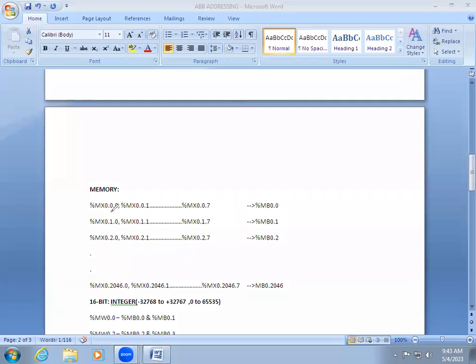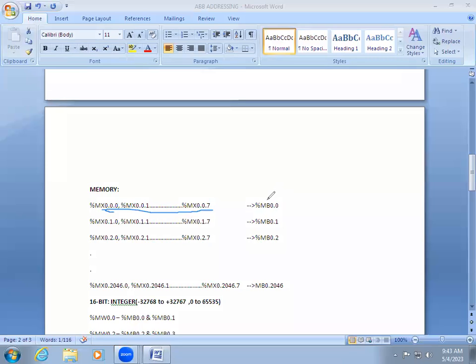In memory addressing, the channel is point zero and the bit is point zero. Each channel has eight bits, which is why the address changes to %MB — B means byte — so 0.0. In each byte we have eight bits. In ABB they have not given any fixed register address.